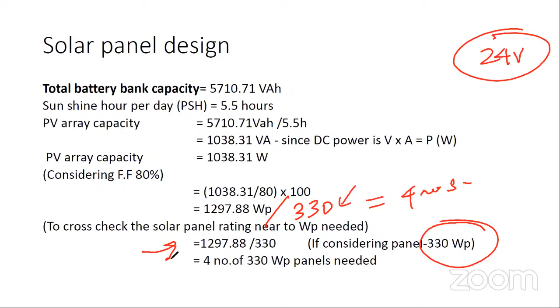To cross check the solar panel rating, we need to choose a panel. Here I am choosing a 330 watt panel. I just need to divide the total PV array capacity by my single PV module wattage. If you divide, you get 4 panels required. Again, the system voltage is 24 volts, and the voltage of a single 330 watt panel is also 24. In order to increase the power, the only option is to connect all the panels in parallel.